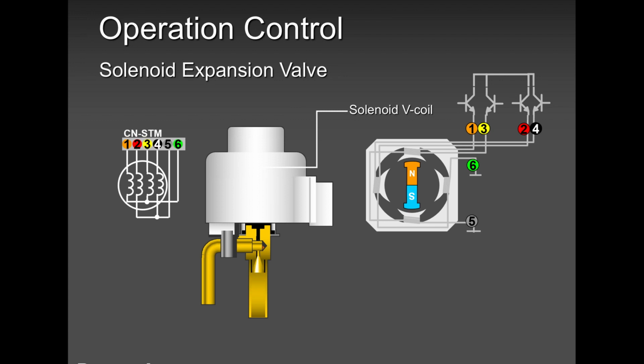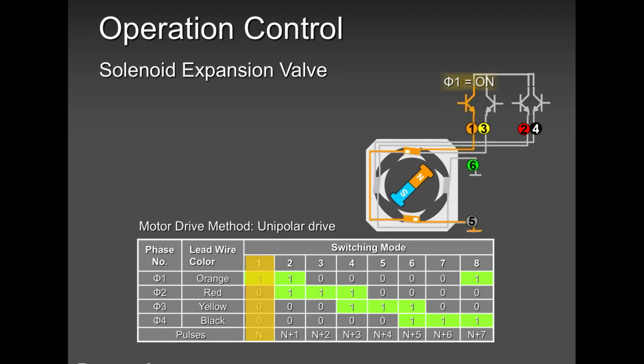Back in the day, we used to call these a capillary tube. A capillary tube was a fixed orifice. The electronic expansion valve is not fixed anymore. It regulates, opens and closes depending on the load that we spoke about 1 or 2 slides earlier. When there's less load, this electronic expansion valve will hardly open. When there is lots of load needed, it will open like crazy to the maximum. And then it will regulate up and down, up and down.